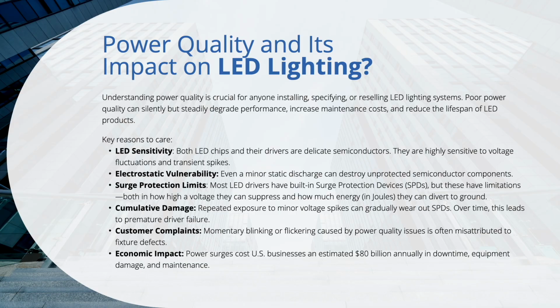Electrostatic vulnerability. Even a minor static discharge can destroy unprotected semiconductor components. Surge protection limits. Most LED drivers have built-in surge protection devices, SPDs, but these have limitations both in how high a voltage they can suppress and how much energy, in joules, they can divert to ground. Cumulative damage. Repeated exposure to minor voltage spikes can gradually wear out SPDs. Over time, this leads to premature driver failure.